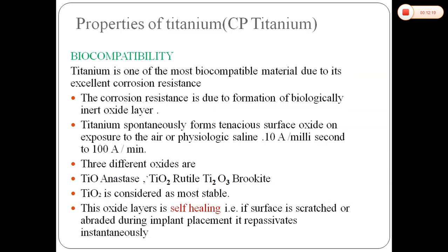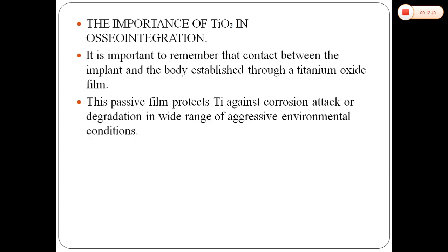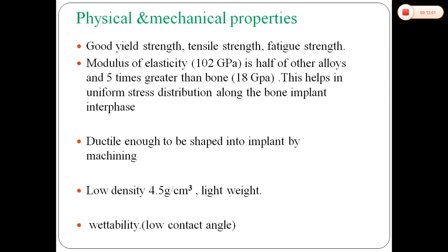The properties of titanium, although already discussed, will be explained again. Regarding biocompatibility: titanium is one of the most biocompatible materials due to its excellent corrosion resistance. Corrosion resistance is due to the formation of a biologically inert oxide layer. It is important to remember that the contact between the implant and the body is established through a titanium oxide film. This passive film protects the titanium, preventing corrosion, attack, or degradation across a wide range of aggressive environmental conditions. Its modulus of elasticity is 102 GPa, which is half of other alloys and five times greater than bone, helping in uniform stress distribution around the bone-implant interface.